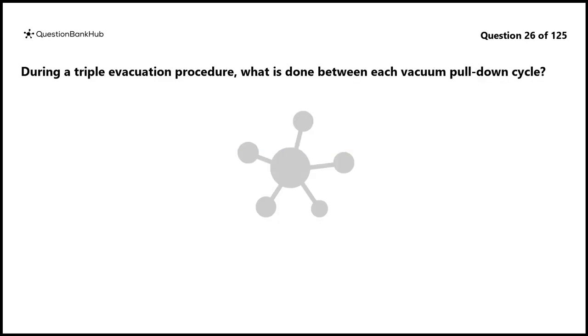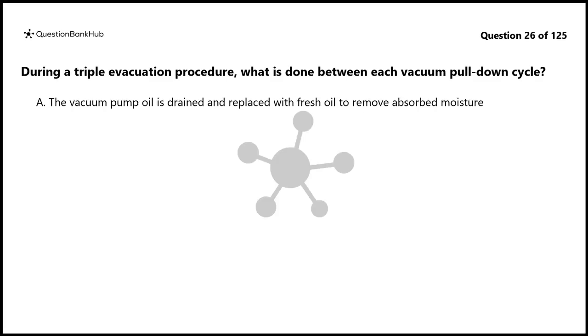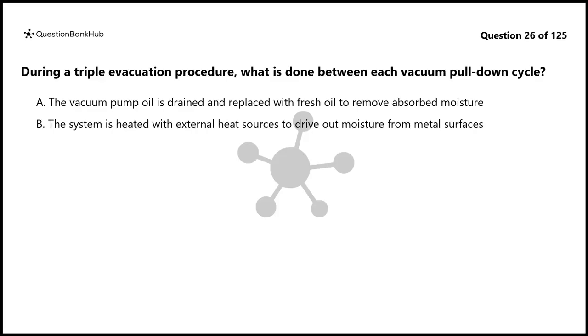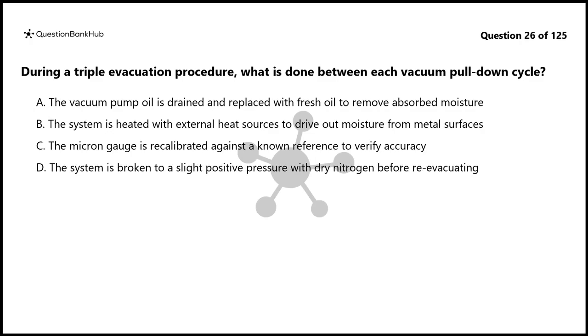Question 26. During a triple evacuation procedure, what is done between each vacuum pull-down cycle? A. The vacuum pump oil is drained and replaced with fresh oil to remove absorbed moisture. B. The system is heated with external heat sources to drive out moisture from metal surfaces. C. The micron gauge is recalibrated against a known reference to verify accuracy. D. The system is broken to a slight positive pressure with dry nitrogen before re-evacuating.